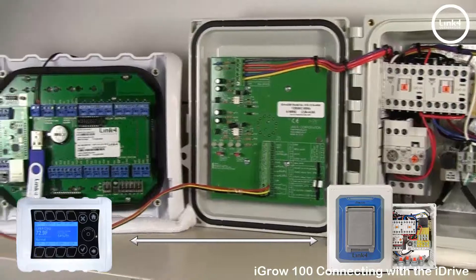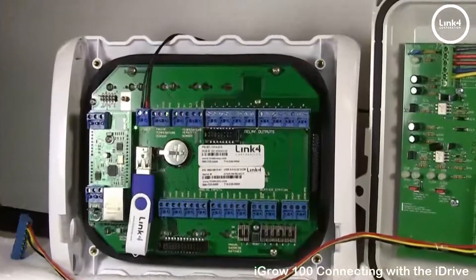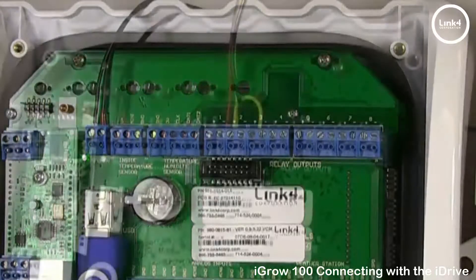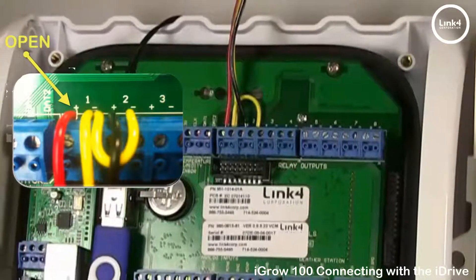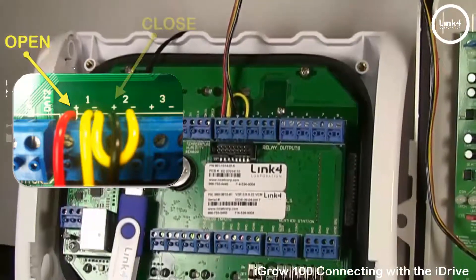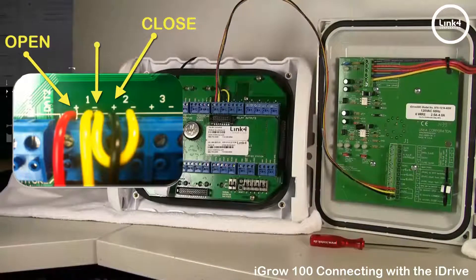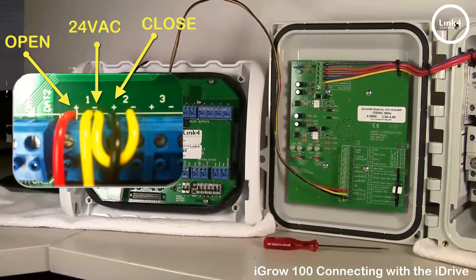Once you reach the iGrow 100 series controller, identify which paired opening you want your wires installed in. For this example, we're using outputs number one and two. The open signal — red wire — lands on positive one. The closed signal — black wire — lands on positive two. The 24-volt common from the iDrive transformer lands on negative one, jumping to negative two, which is the yellow wire.